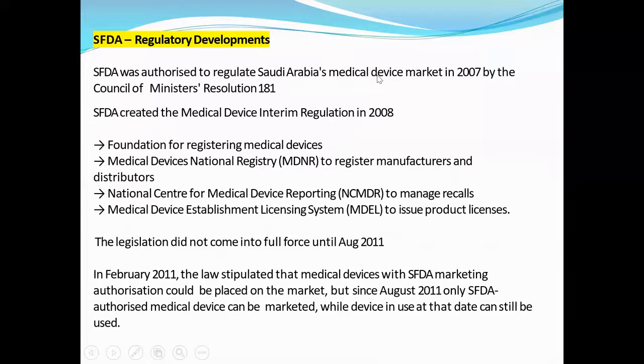So what is the regulatory requirement in Saudi Arabia? The SFDA was authorized to regulate Saudi Arabia's medical device market in 2007 by Council of Ministers Resolution 181. The SFDA created the Medical Device Interim Regulation in 2008. Then came the foundation for registering medical devices, the Medical Device National Registry, that is MDNR, to register manufacturers and distributors; the National Center for Medical Device Reporting, that is NCMDR, to manage recalls; and the Medical Device Establishment Licensing system, that is MDEL, to issue the licenses.